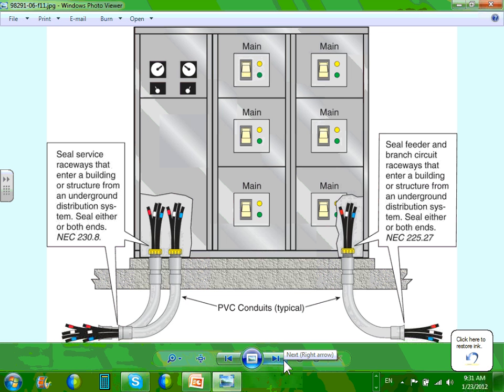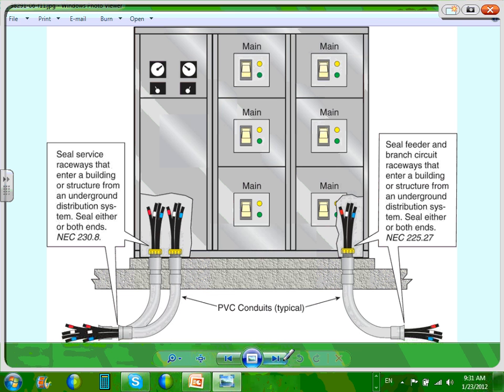Okay, this is interesting because it came in 2011 and even before. If you bring in feeders from the underground, you have to seal. You have to seal right here or at the same location, either one location. You're bringing a feeder, most likely coming from underground. What do you think the conduit would be? Your conduit of choice, PVC, always underground. You're coming from underground into the switchgear, guys.